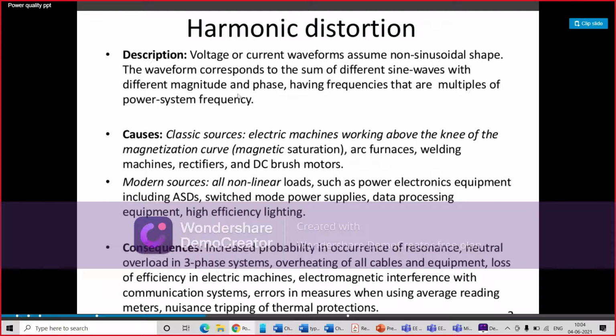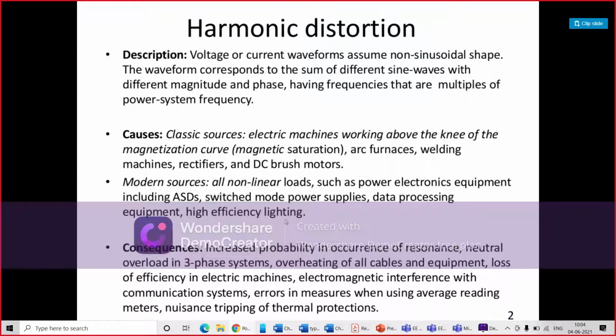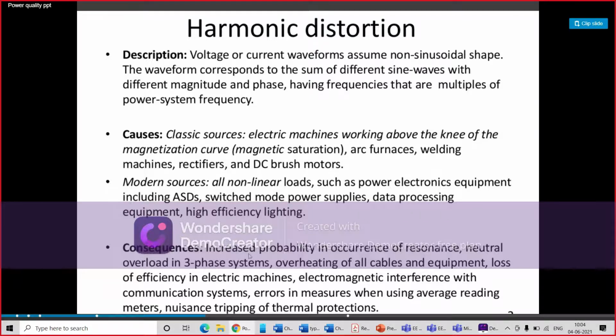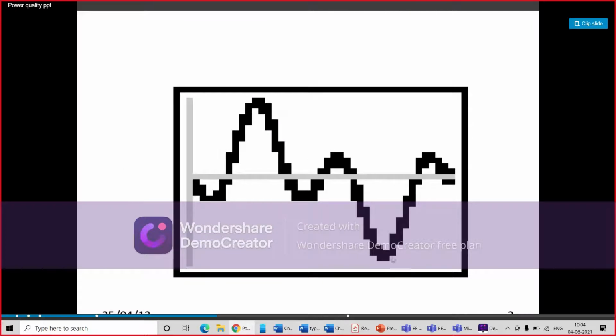Then after this swell, you have this harmonic distortion. What is harmonic distortion? Voltage or current waveform assumes a non-sinusoidal shape. The waveform corresponds to the sum of different sine waves with different magnitude and phase, having frequencies that are multiples of the power system frequency. What are the different causes? Electrical machines working above the knee of the magnetizing current, arc furnaces, welding machines, rectifiers, DC brushes, modern sources, for example non-linear load, power electronic equipment, and so on. And what are the consequences? Increased probability of occurrence of resonance, neutral overload in three-phase systems, overheating of cables, loss of efficiency, electromagnetic interference, and so on. These are the consequences of your harmonic distortion. It looks like this.